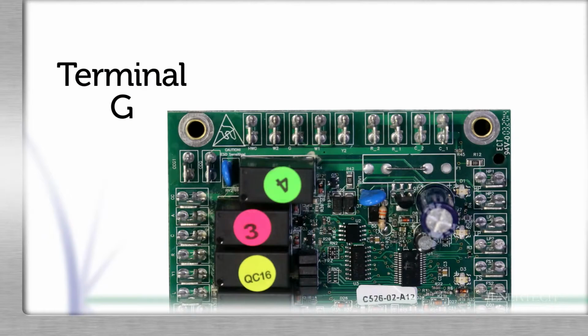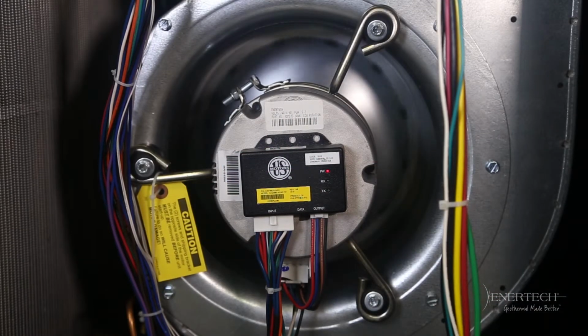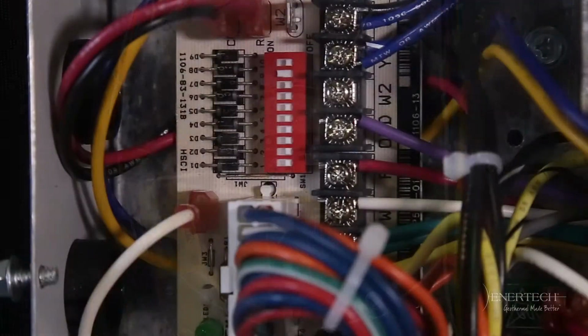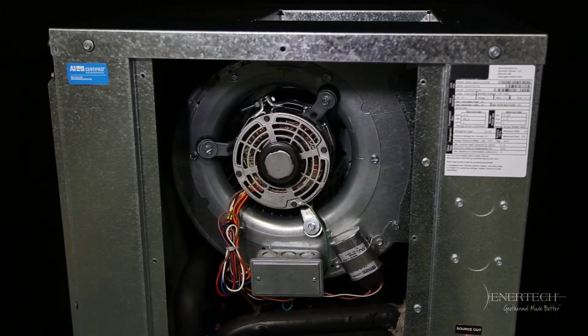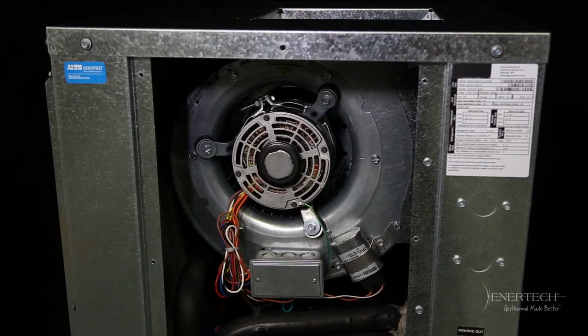When an ECM control module receives a G call without a call for heating or cooling, the fan operates at 50% of the full load airflow CFM level based on dip switch settings. VS units with the PSC fan start at 100% airflow level immediately after the G input.